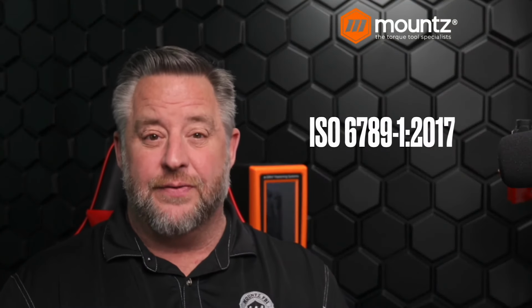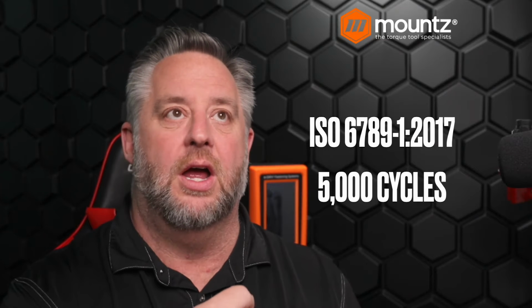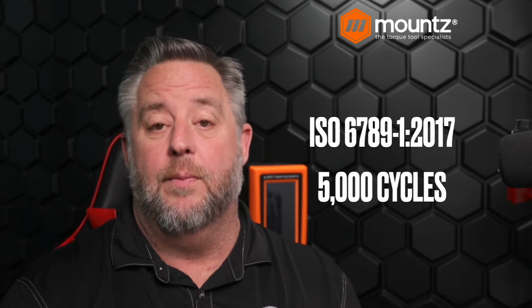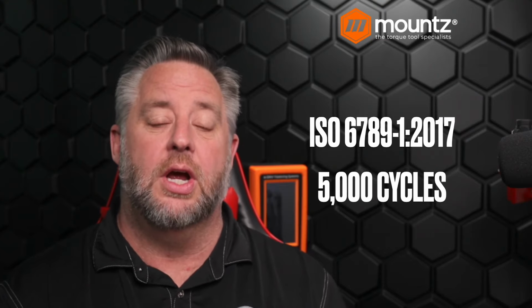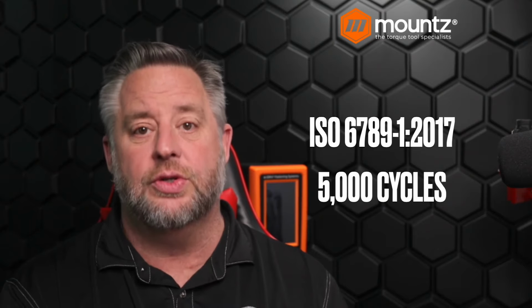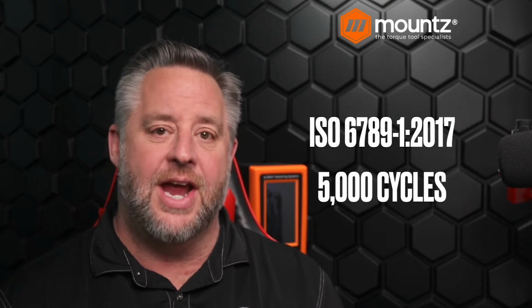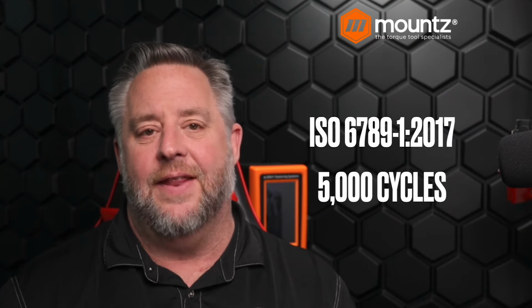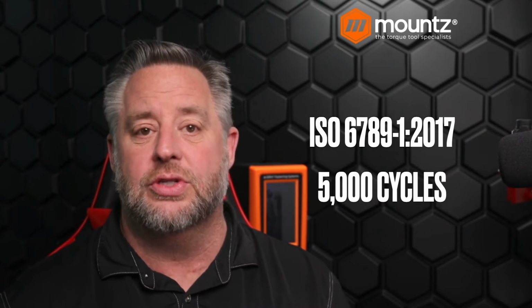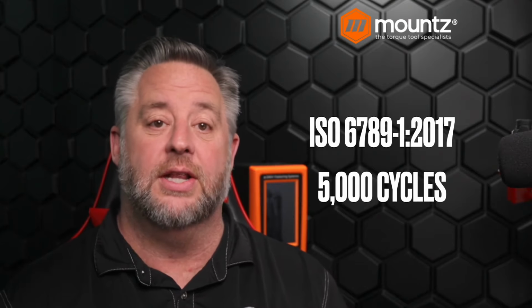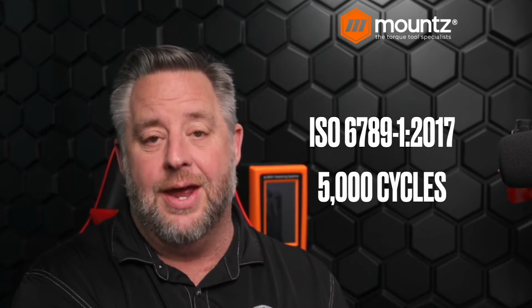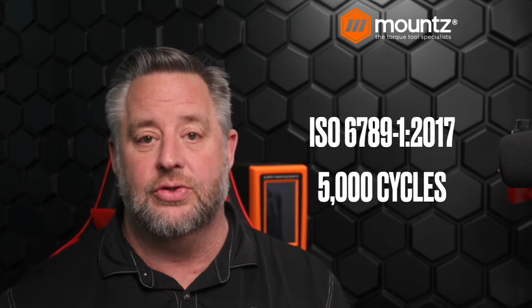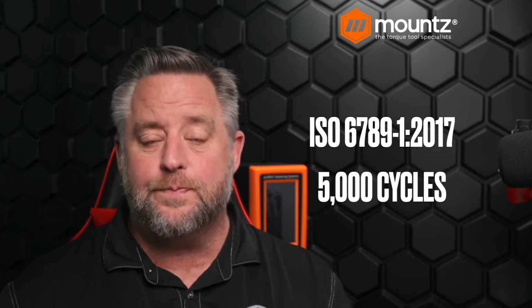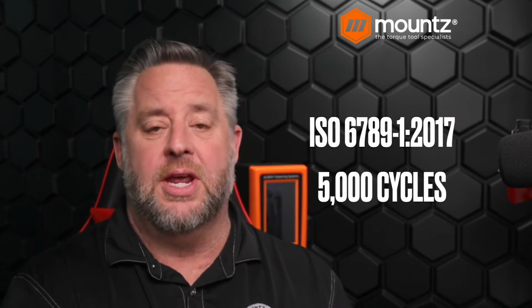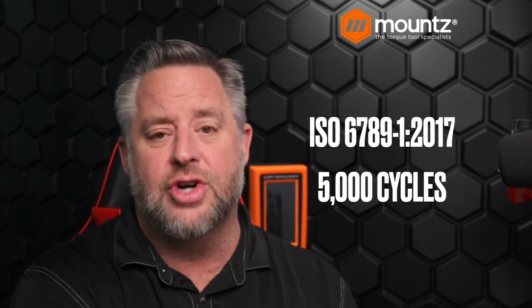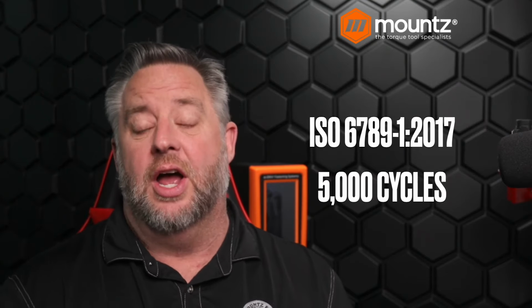And there are several different types of calibration cycles. Now, typically, most torque hand tools are going to be a classification of an ISO 6789 tool. And that classification states that those tools must remain in calibration for at least 5,000 cycles to be considered an ISO 6789 tool. And that could be either a torque screwdriver or a torque wrench in those classifications.